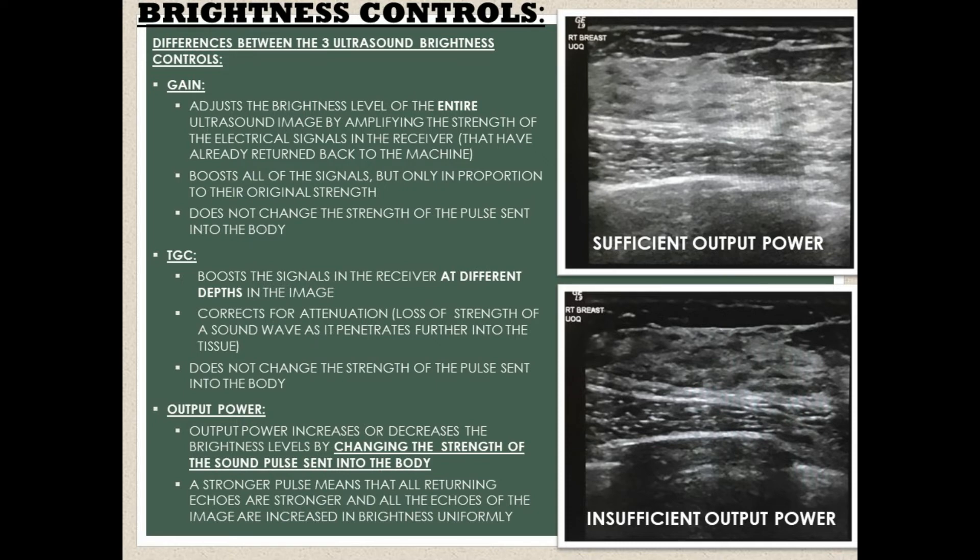In the images to the right, an insufficient output power is used in the bottom image, and you'll note how dark the image is. In the top image to the right, a sufficient output power is used, and you'll note that the image has sufficient brightness.